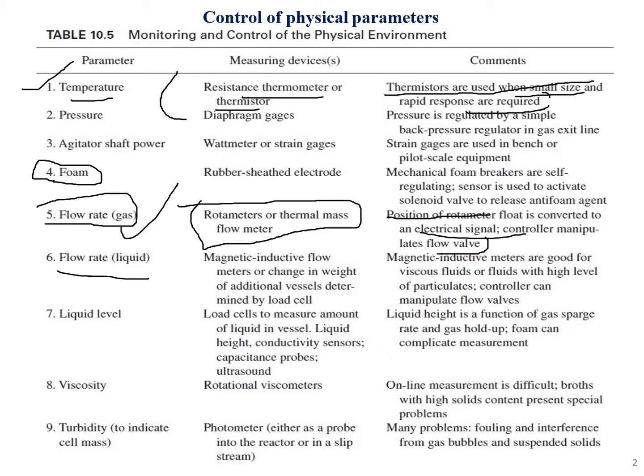The sixth point is flow rate for liquid. This is measured with the help of magnetic inductive flow meters, or by change in weight of additional vessels determined by a load cell. Magnetic inductive meters are good for viscous fluids or fluids with a high level of particulates.